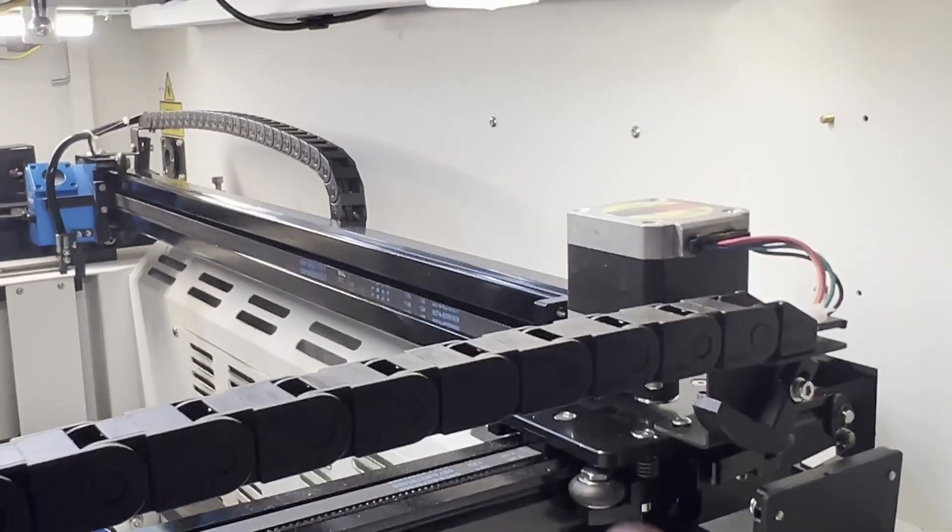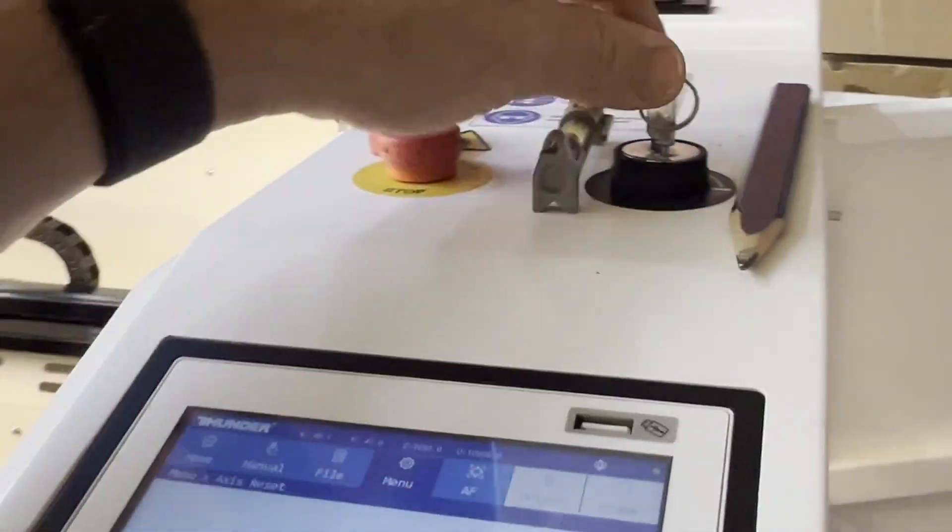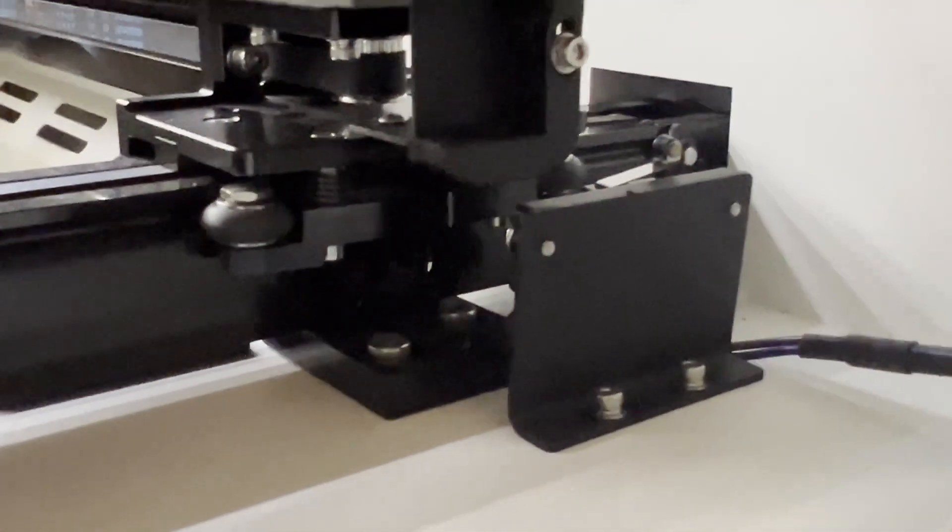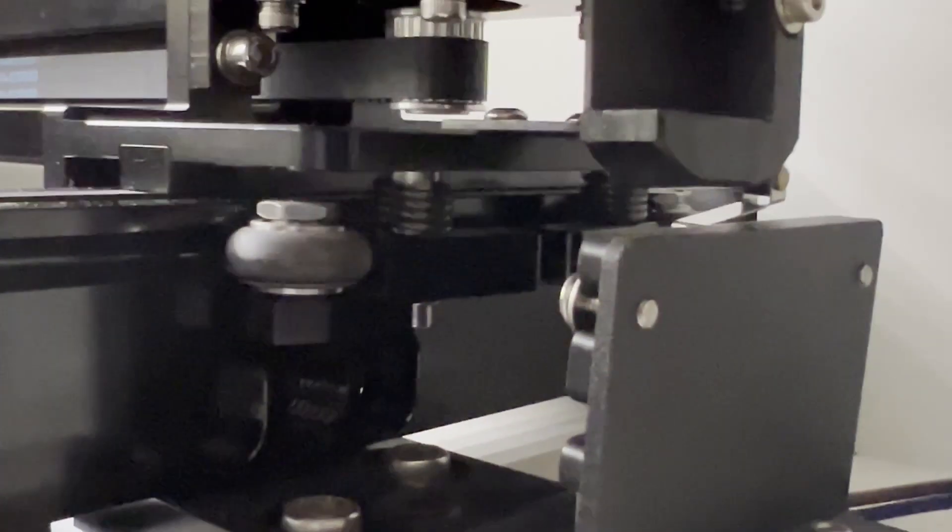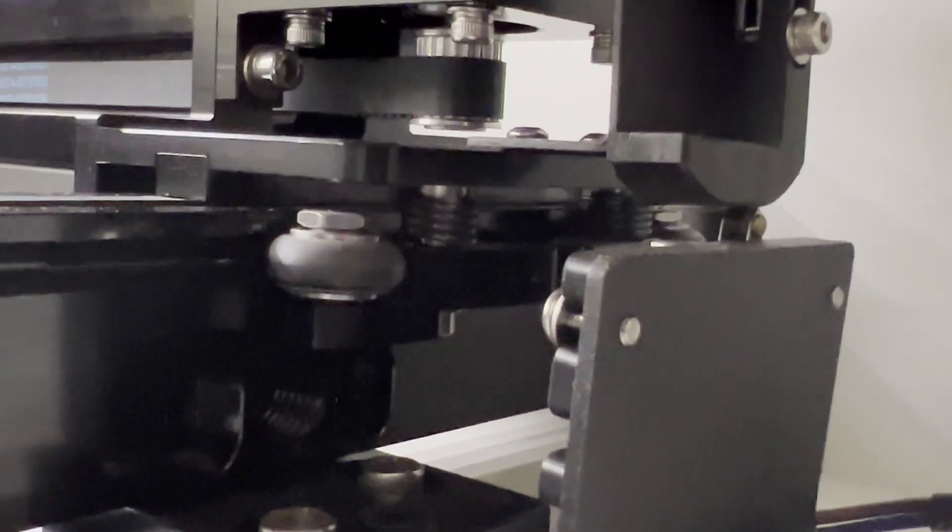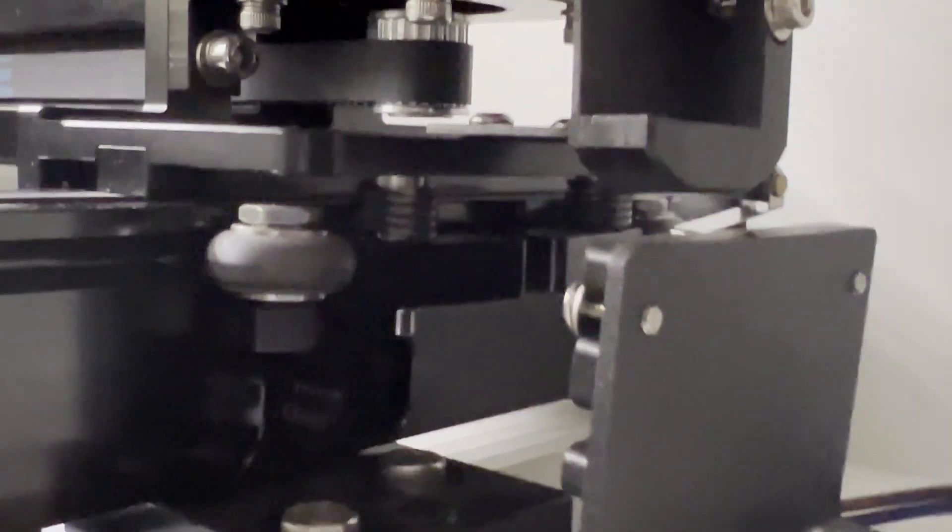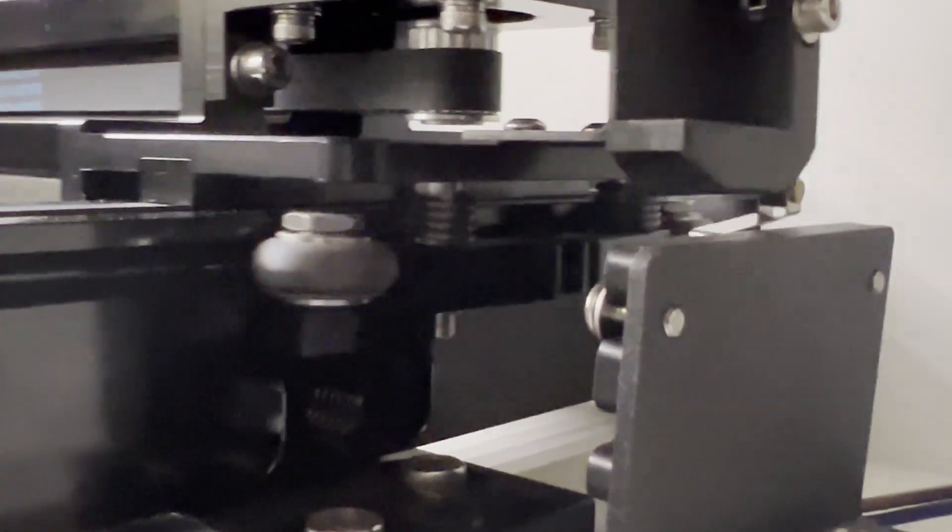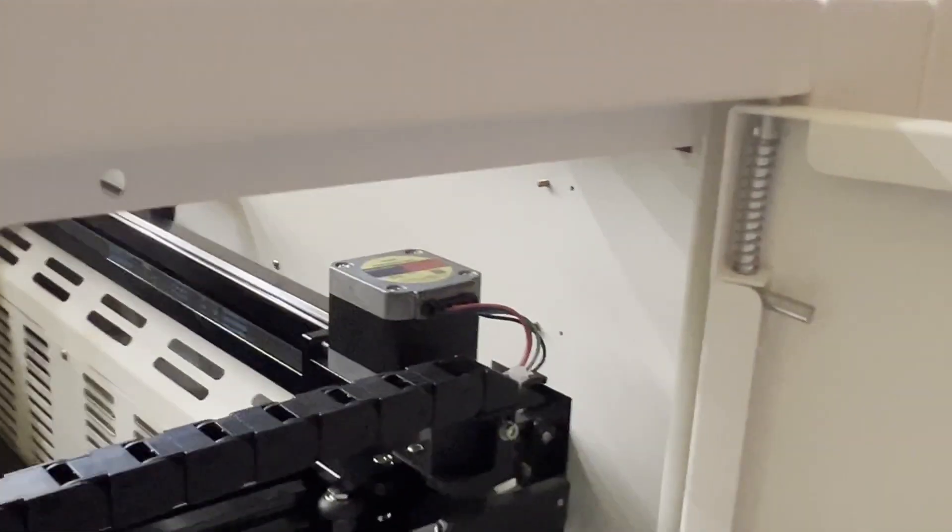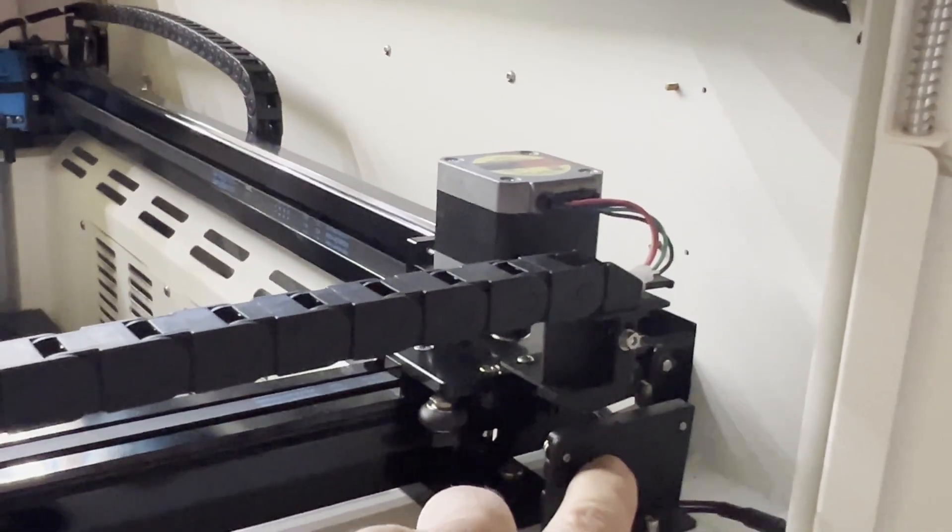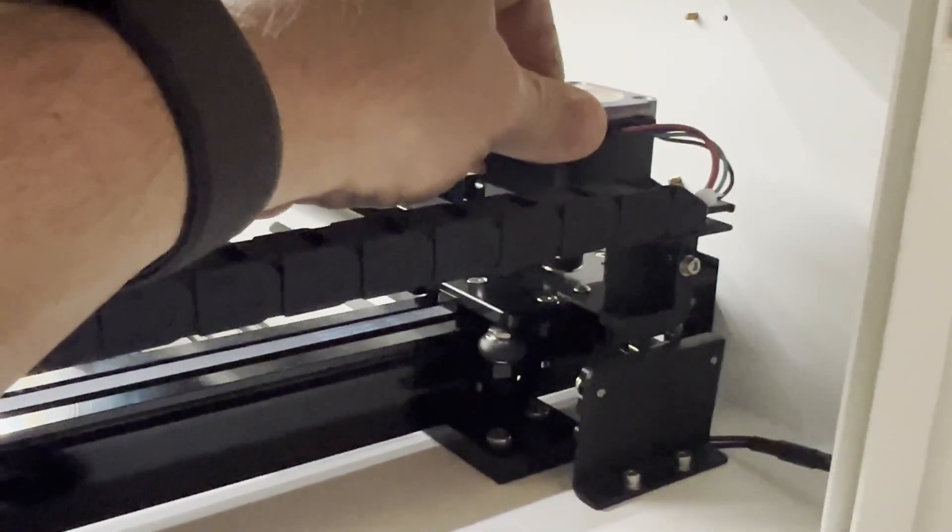So what I'm going to do is actually show you. I'm going to shut the machine off and show you manually when I push this, how this is supposed to operate. So you can see that is clicking the switch. Now that doesn't necessarily mean that is actually triggering the switch. We need to make sure both on the controller using our LED lights or on our screen that it is making contact and electronically telling the machine and the controller that it is at its limit.